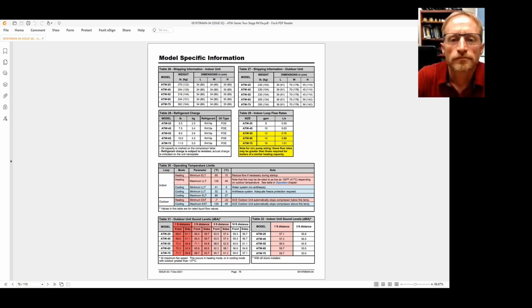So there's no issue with having antifreeze in the system in heating mode then? No. Any antifreeze has a little bit less heat transfer capacity than water, but it matters mostly at higher concentrations of propylene glycol, which you might actually be using. Propylene glycol is a non-toxic antifreeze, and it's the most common one used these days because it's not poisonous. But as opposed to methanol or ethanol, propylene glycol is harder to pump and has significantly less heat transfer capacity than water. So it does introduce a bit of a disadvantage if you have to use a high concentration of propylene glycol.